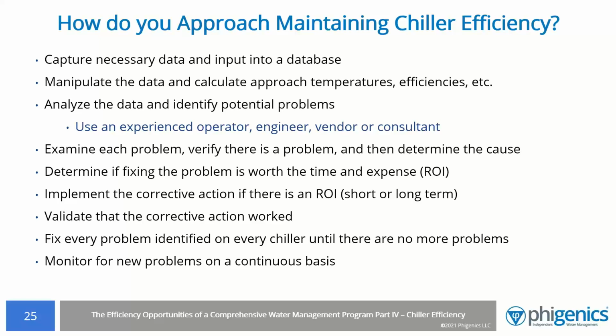Then determine if fixing the problem is worth the time and expense. Is there a return on your investment of maintenance dollars? Do you really need to open the chiller up? You then implement the corrective action. Then you need to make sure that the corrective action actually worked. And then you go through and fix every problem on every chiller. And then you start all over again and monitor for new problems on a continuous basis. Sounds easy, right? We'll go through some of the steps in more detail in the next few slides.